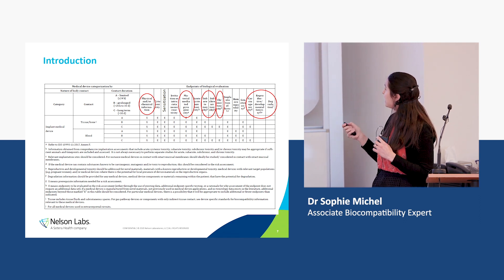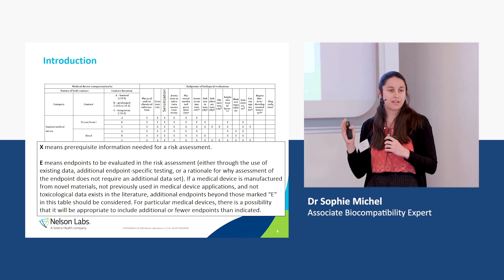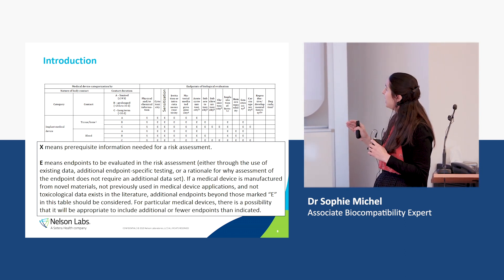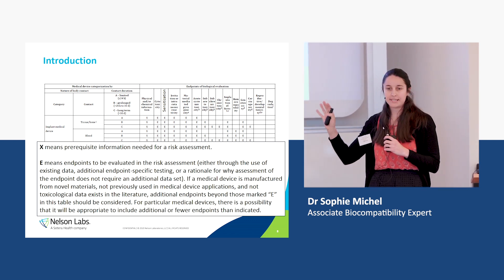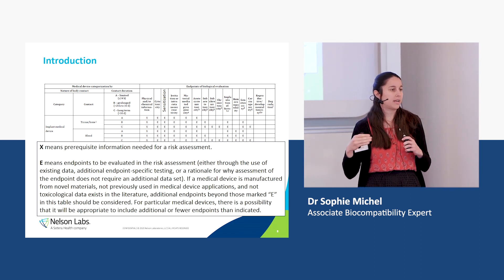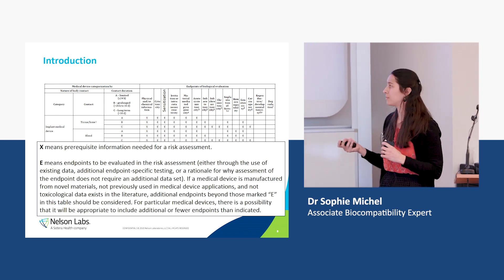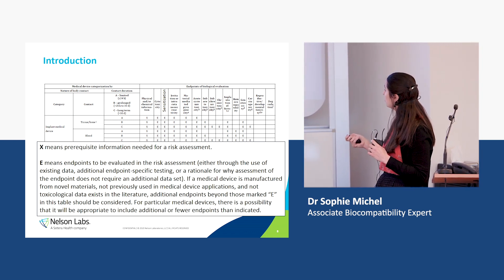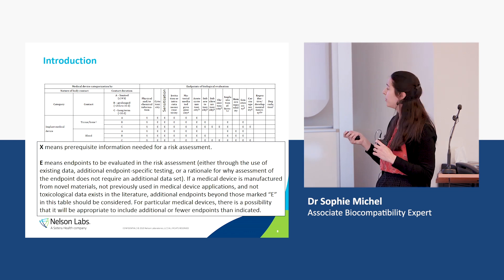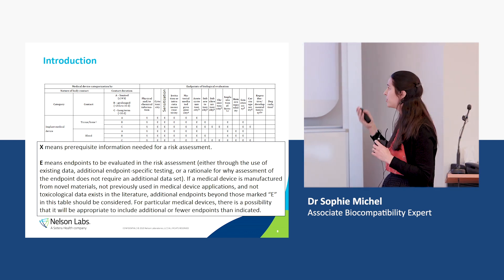Then come all kinds of X and E designations. X is defined as prerequisite information — this is the only mandatory step, the only thing you really need to do for any kind of medical device. E means an endpoint that needs to be evaluated either through testing or by other means, for example literature data, historical data on a prototype, a previous device, a predicate, or data on your raw material from your suppliers. It's also very important to note that there is a possibility that it will be appropriate to include additional or fewer endpoints than indicated on the chart.